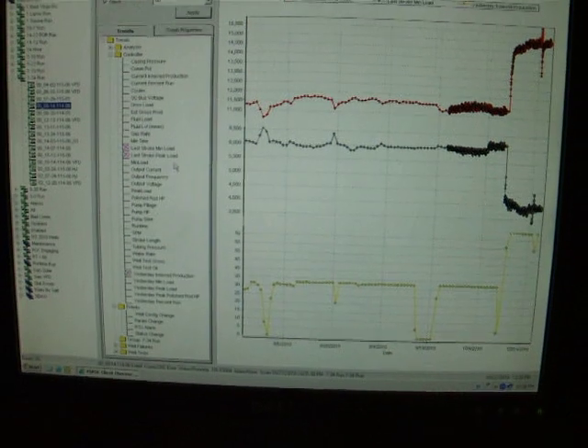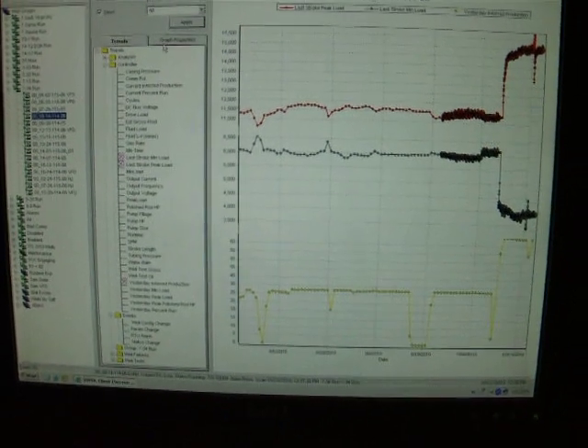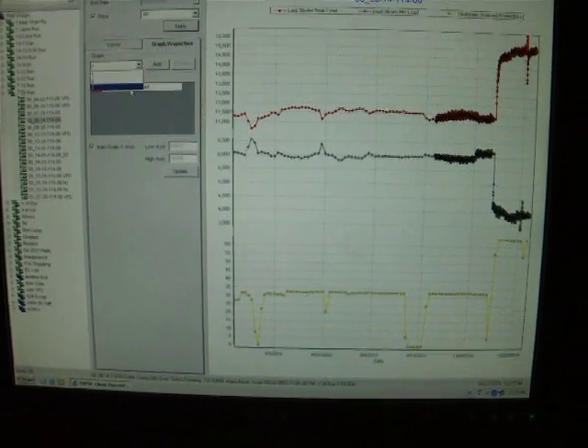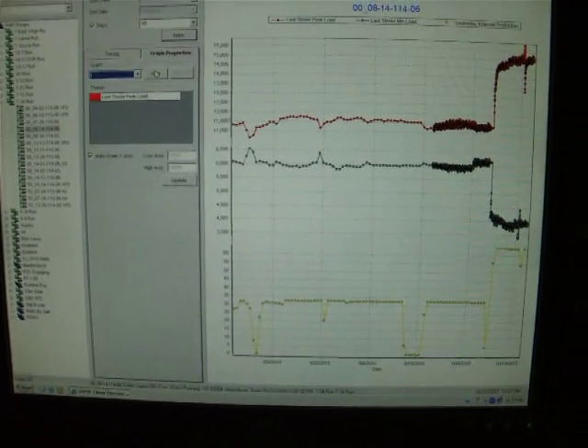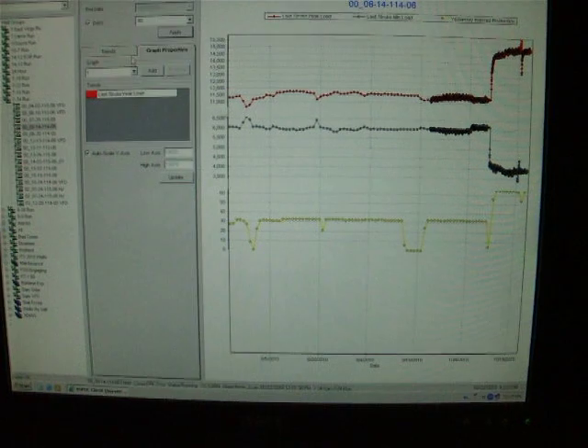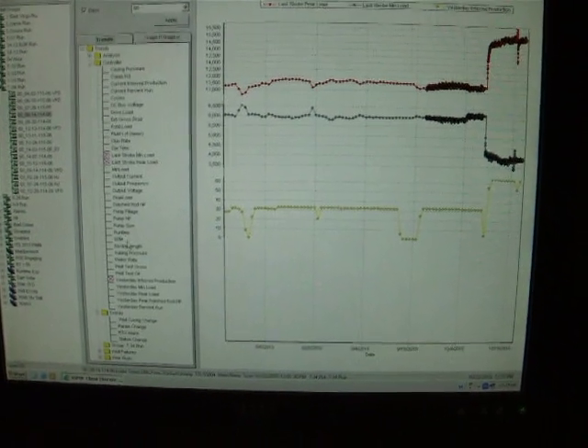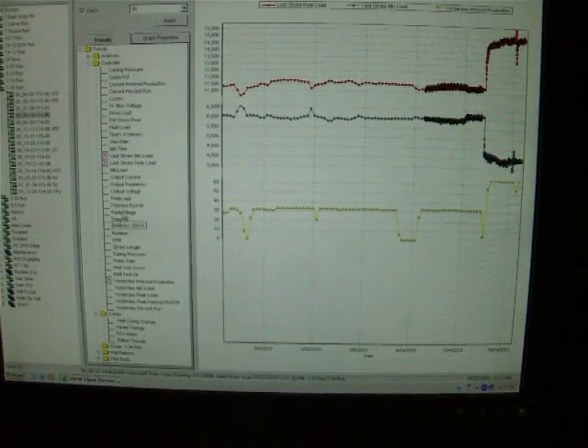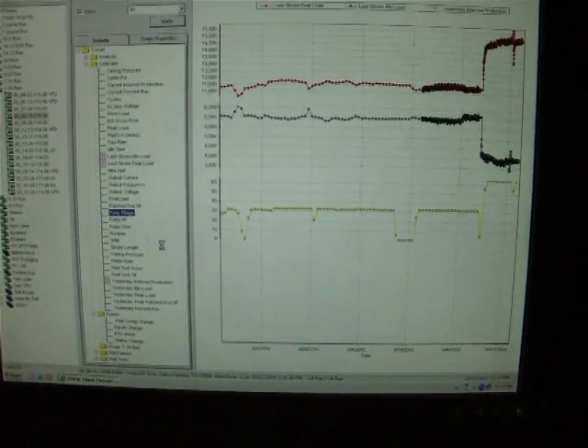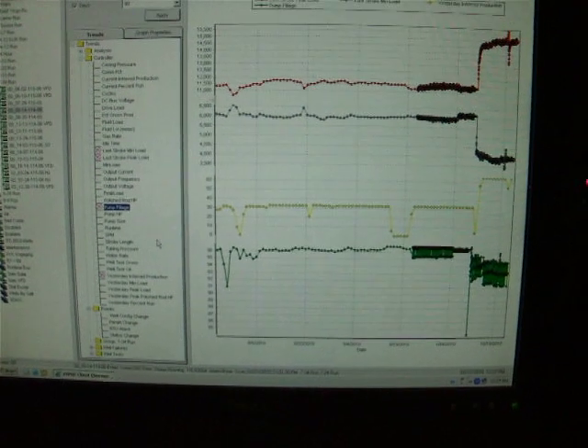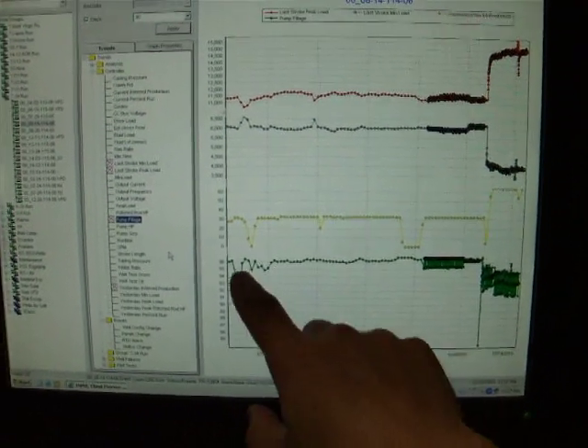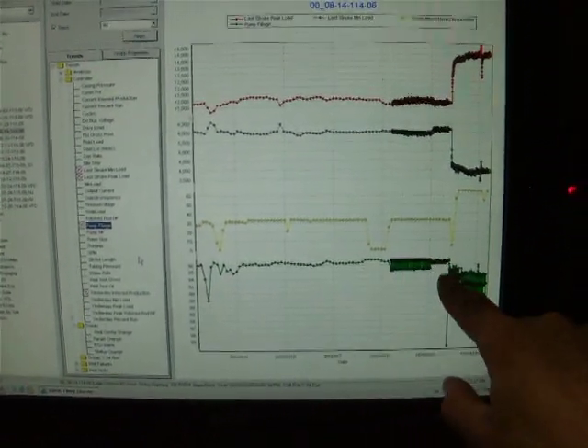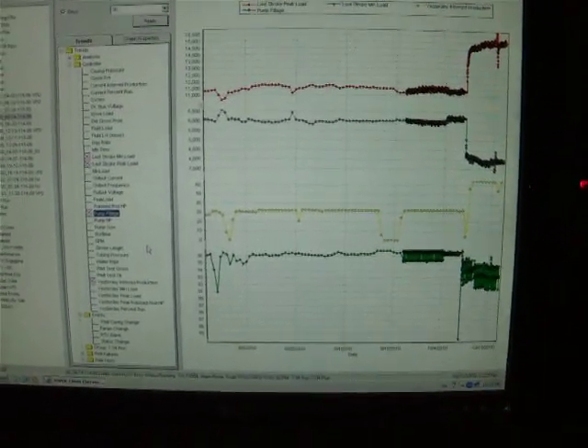And if I want to see what the pump fillage was doing during that time, I can add a fourth trend, put in the pump fillage. And our pump fillage was running around 96% the whole time and actually dropped off a little bit.